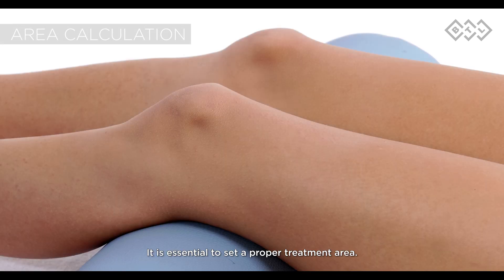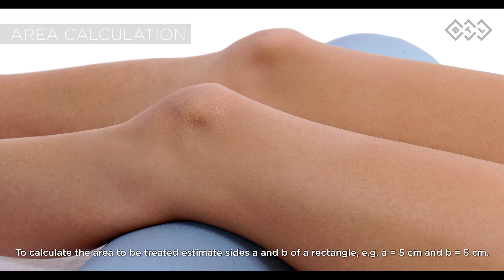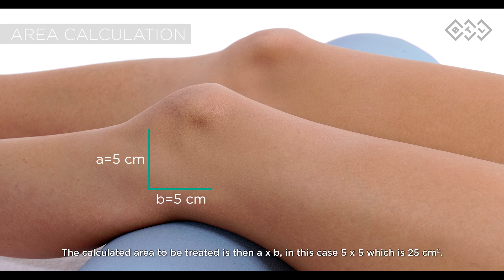It is essential to set a proper treatment area. To calculate the area to be treated, estimate sides A and B of a rectangle. For example, A equals 5 cm and B equals 5 cm. The calculated area to be treated is then A times B — in this case 5 times 5 — which is 25 cm².